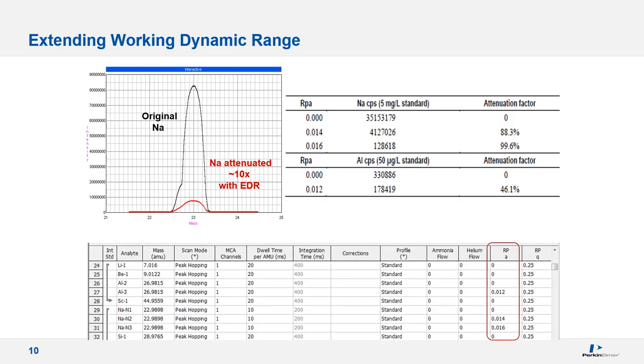The table on the right of this slide shows the equivalent electronic dilution achieved with increasing electronic settings on the universal cell quadrupole setting rejection parameter A. You can run elements with multiple EDR settings to aid during testing and method development, or to cover all the concentration ranges of your samples. The RPA or high mass cutoff setting on the universal cell is increased slightly; voltages of 0.008 to 0.016 are suggested starting points to detune the ion beam as it passes through the cell. Elements in both normal and EDR mode can be calibrated at the same time, leading to extended dynamic range in the hundreds of ppm.